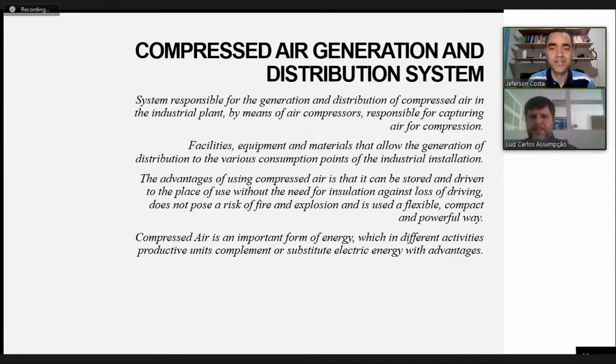In the air system, let me add, you have the air compressor, and depending on what you do with the air, it can have different specifications. For instance, in the refinery we have the service air that is used to purge and clean machines, equipment, or instrumentation. And we have the instrument air that is used to actuate pneumatic instrumentation, control valves, or even some pneumatic equipment. So if your air is used as instrument air, the quality is different from the service air, but your source can be the same air compressor. So you need to evaluate the flow and pressure. That's very nice, Luis.